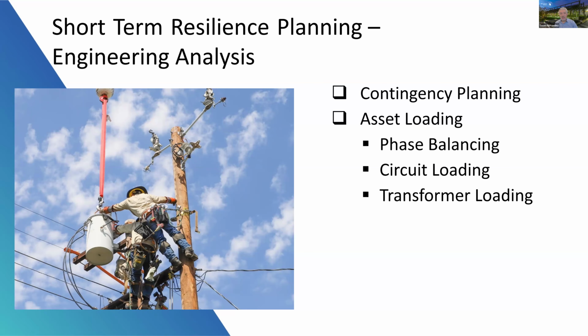And what we do is we check to see whether any circuits are overloaded near our planning criteria. To the extent we can shift those loads from one circuit to another, we'll do that. But if it's going to take major upgrades, such as a brand new feeder or a brand new substation, it's just something that we'll have to address in our overall electric distribution master plan and capital plan. We do look at substation transformer loading and distribution loading ahead of the summer as well. Substation transformer loading is a little bit more difficult to accomplish, so that's usually handled from a capital planning standpoint. Distribution transformer loading is something that we definitely handle every year and try to pick off the most heavily loaded transformers. Next slide, please.